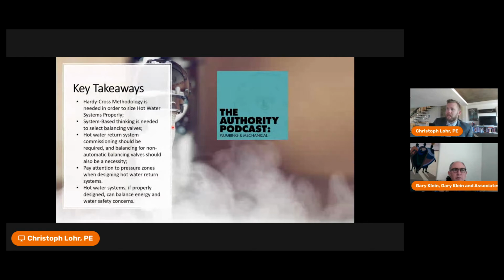So just some key takeaways. Again, Hardy-Cross methodology is needed. We need to look at our whole system. Commissioning should be required, and balancing for non-automatic valves should be an absolute necessity. Paying attention to pressure zones is vital, and so is hot water systems design that can balance energy and water safety concerns.